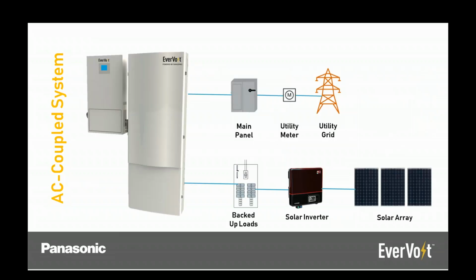AC coupled, in this example, you're going to already have a PV inverter. In this case it's a string inverter, but it can just as easily be microinverters or optimizers or whatever other technology comes our way. That system is kind of separate from your energy storage system. The energy storage system can interact somewhat with the PV array, but essentially they're two separate systems.